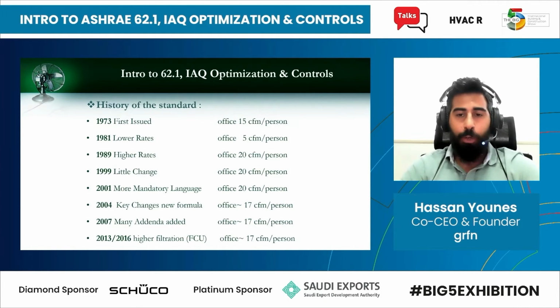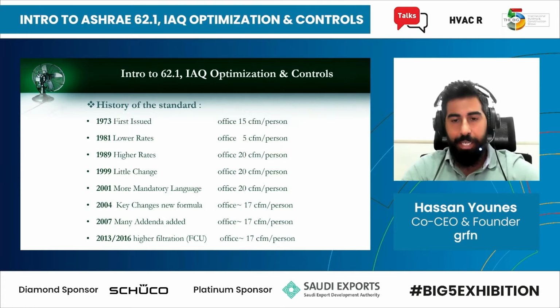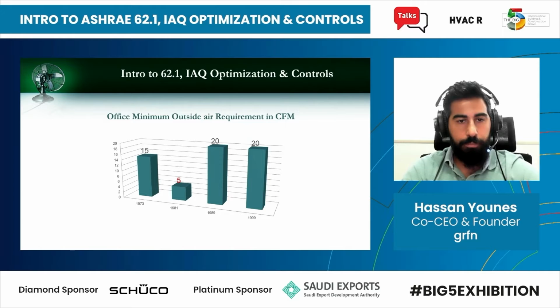But in terms of the quantity per person, as a general comparison, it kind of went back to 1973 in terms of quantity. So it's almost 17 CFM per person when taking into account the area that is occupied by one person in an office building, which is normally taken as one person per 20 square meters. That's just a representation of what we just talked about.